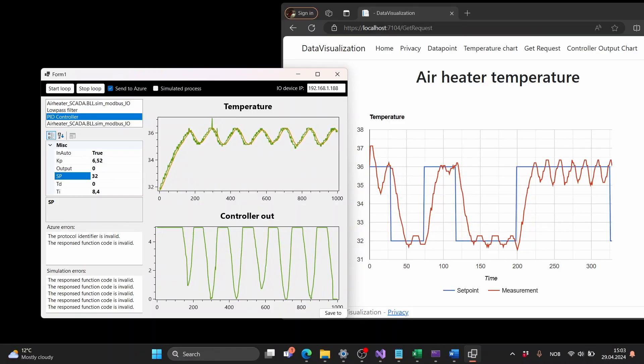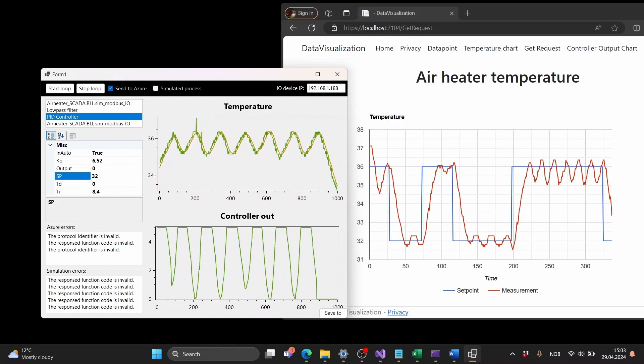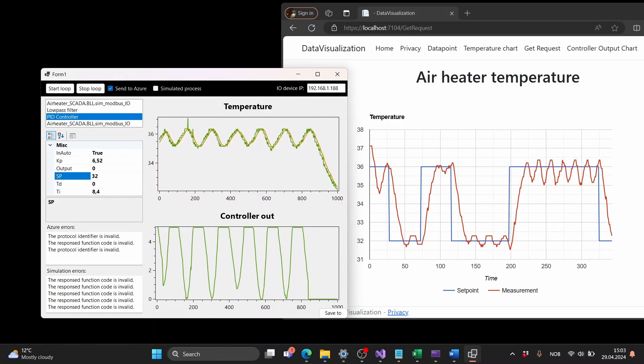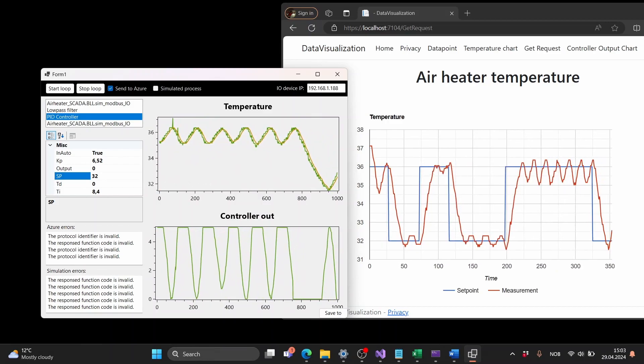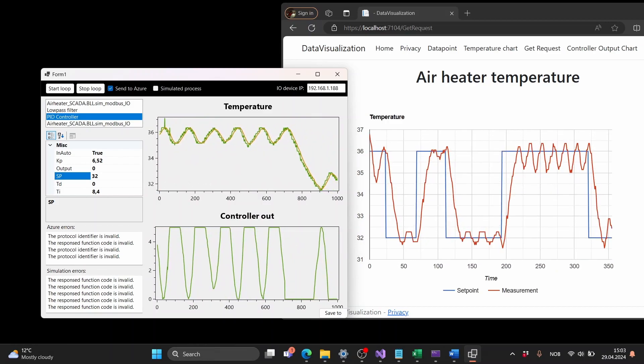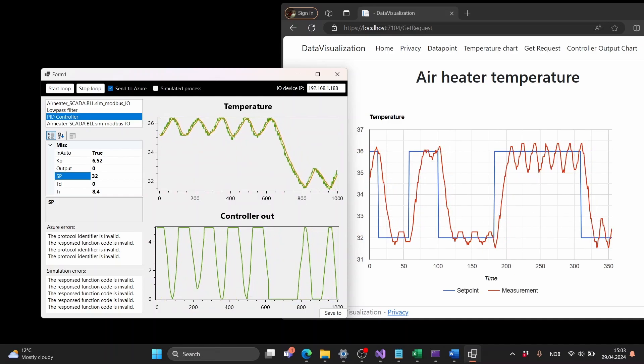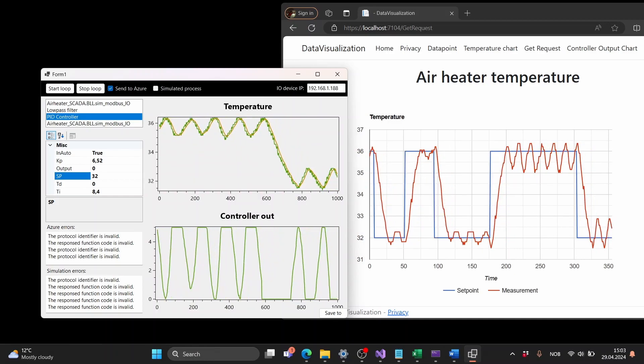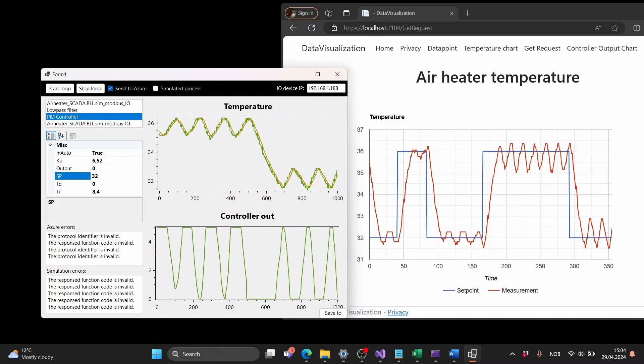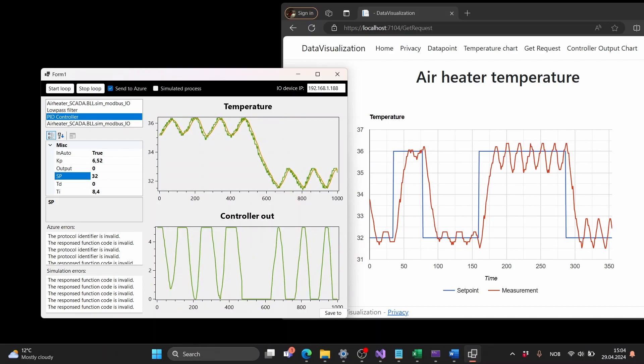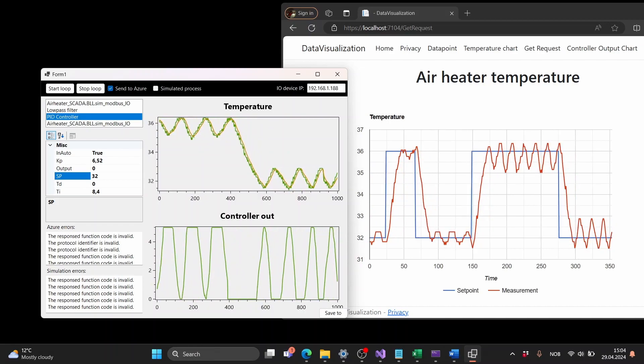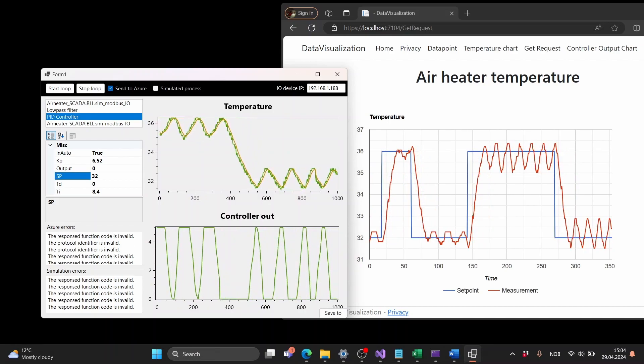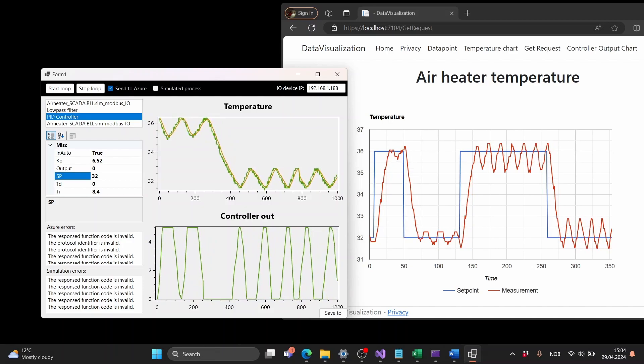Now it's time to tune the PID controller to get good stability. As you see right now the red value is close to the setpoint in blue but it is very unstable. So here we need to do some tuning. On this kind of process we don't need the D parameter so we only need to tune the Kp and Ti parameters.